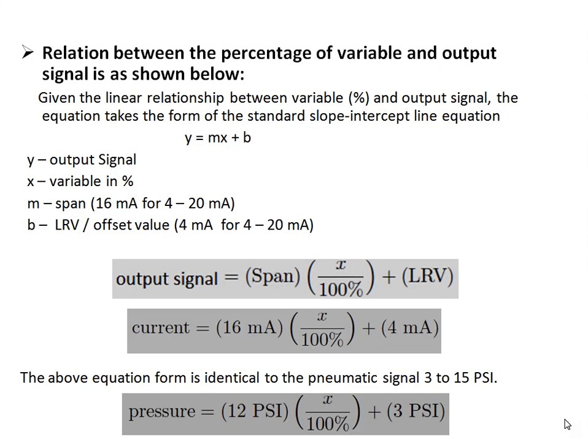The relation between the percentage of the variable and output signal is shown below. Given the linear relationship, the equation takes the form of the standard slope-intercept line equation: y = mx + b. Here y is the output signal, x is the variable in percentage, m is the span — which is 16 mA for 4 to 20 mA signal — and b is the lower range or offset value, which is 4 mA for the 4 to 20 mA signal range.